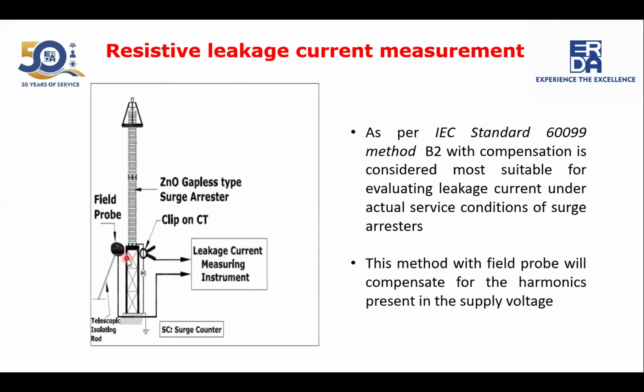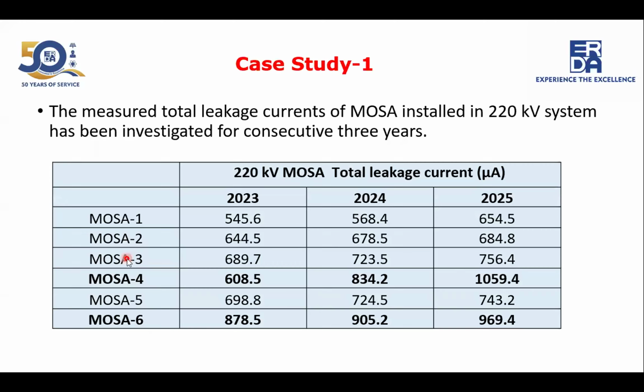So this is how we measure the leakage current flowing through the surge arrestor, and we see the trend analysis of the leakage current, and based on that we decide the healthiness of the surge arrestor. Here we have shown two case studies. One case study is of a 220 kV surge arrestor. There are a number of surge arresters connected in the substation. We measured six surge arresters of 220 kV rating, where we measured the total leakage current. The unit is microampere peak. We measured the first reading in 2023. Then after 1 year, in 2024, the same measurement was carried out on the same surge arrestor, and then again in the third year, this year 2025, we did the measurement of the total leakage current.